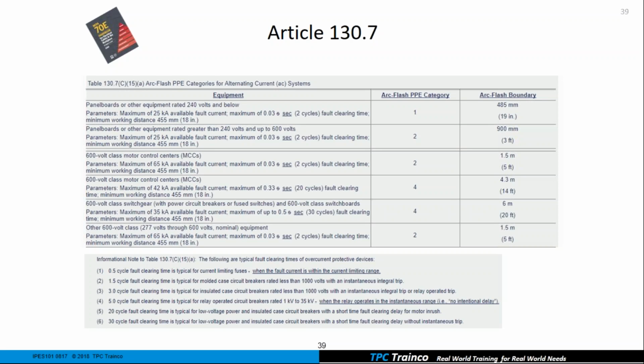So that's great. Well, people might want to just say, oh, you know what? I've got a 208 Y circuit lighting panel over here, so I know it must be PPE category 1. Well, you can't really say that because voltage is not one of the determining factors of incident energy. You can see underneath that statement, panel boards or other equipment rated 240 volts and below, we have parameters. So to be able to use this table, we have to satisfy those parameters.